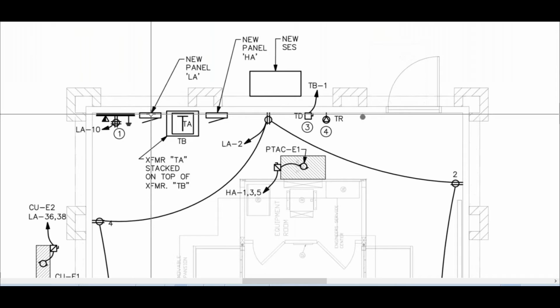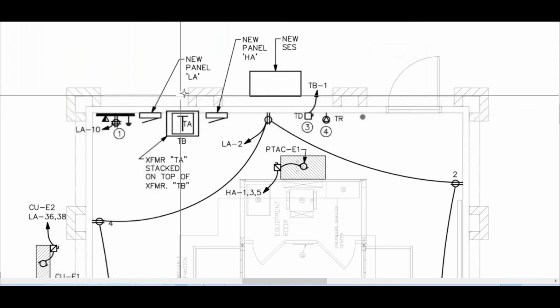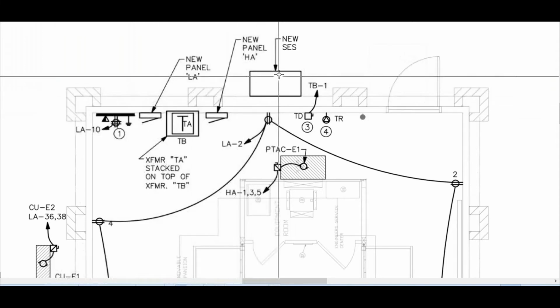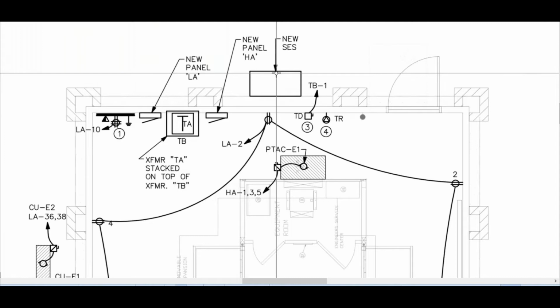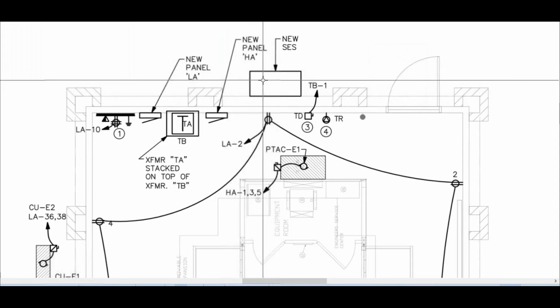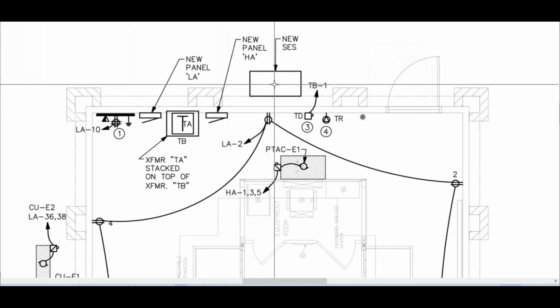Here's my point. When you're estimating things like this, you have to make sure that you include everything. In this instance, this is a weatherproof panel. It's outdoors, and you're required to penetrate the top of that panel with Myers hubs. So on your material takeoff, you would include Myers hubs.